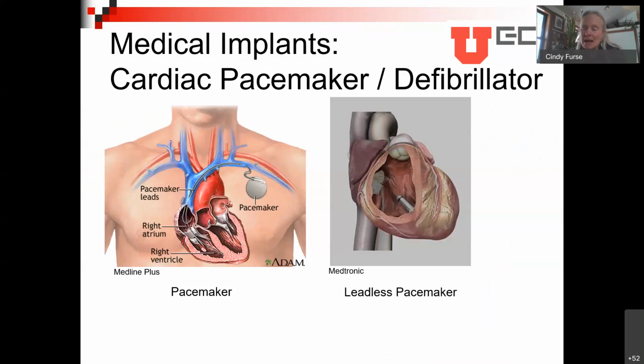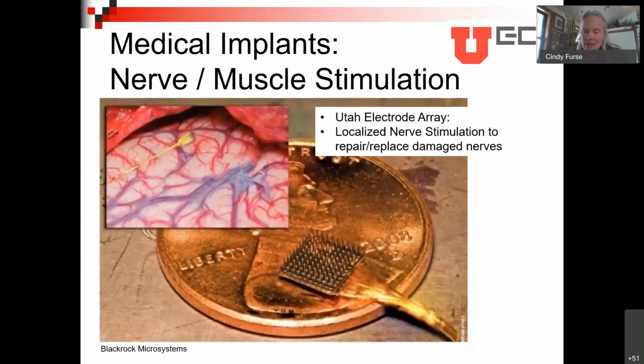So here's an example of the Utah electrode array. You could see there are a bunch of little points on this little electrode right here, and it can be pushed into the brain or a nerve or any other place that needs to be stimulated. This is the electrode array typically used in the back of the eye, for example. It's 4 millimeters square. The electronic devices today are all wired. See how this cable's kind of coming out the bottom? That's a whole bunch of little wires that are connected to each electrode independently. Very important that they're independent in order to be able to get the sight or the brain stimulation or in fact the brain recording that we might want to do.